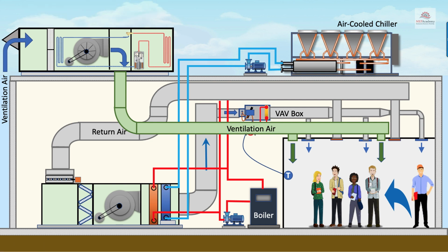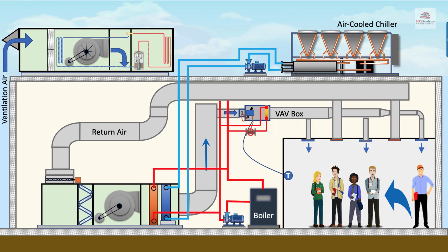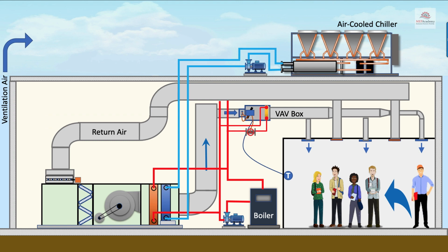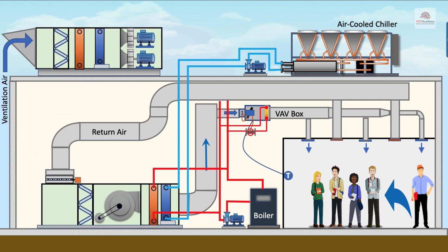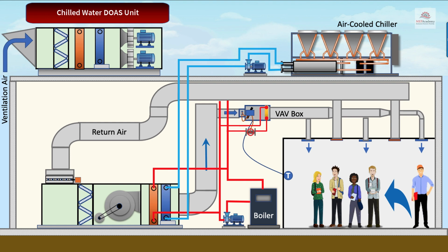We can also keep the same chiller and use the extra capacity to feed a chilled water coil located within a DOAS unit. The air handler's cooling coil can be reduced as it doesn't have to handle the latent load from the incoming ventilation air. The DX DOAS unit can be removed and a chilled water DOAS added to handle the ventilation air.